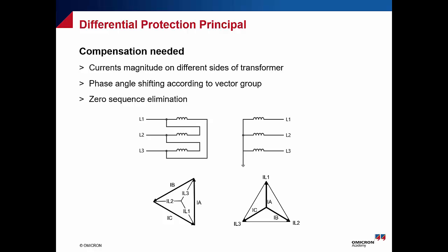And also we have a different CT ratio on both sides. This also makes it a little bit complicated compared to line differential, which has the same voltage and sometimes, mostly, the same CT ratio on both sides.